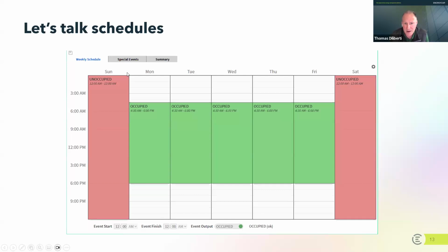Hopefully you can see my mouse as I hover over this special events schedule. I've got a screenshot of that in a second, but it's a way of scheduling events. And once again, the system has to prioritize. Is it going to listen to the weekly schedule first and foremost, or the special events schedule? Understanding the priorities is really important to make sure that you're scheduling your system correctly.